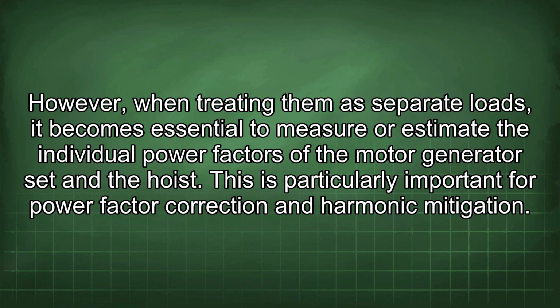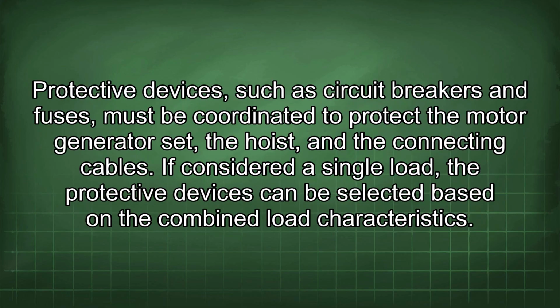However, when treating them as separate loads, it becomes essential to measure or estimate the individual power factors of the motor generator set and the hoist. This is particularly important for power factor correction and harmonic mitigation. Protective devices, such as circuit breakers and fuses, must be coordinated to protect the motor generator set, the hoist, and the connecting cables. If considered as a single load, the protective devices can be selected based on the combined load characteristics.